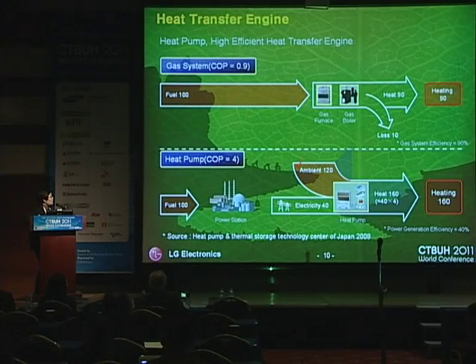But if you have a heat pump for heating, you make 160 kilowatts of heat, because 100 units of fuel make 40 kilowatts of electricity, and then you input the electricity into the heat pump, and you make 160 kilowatts of heat, because heat pump performance is 4 times the input electric energy.